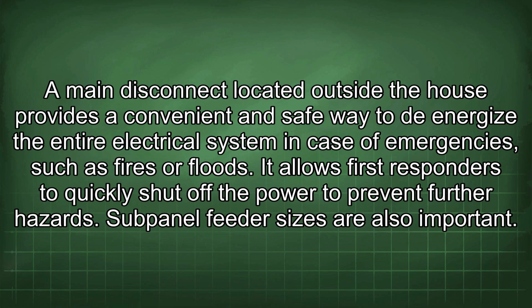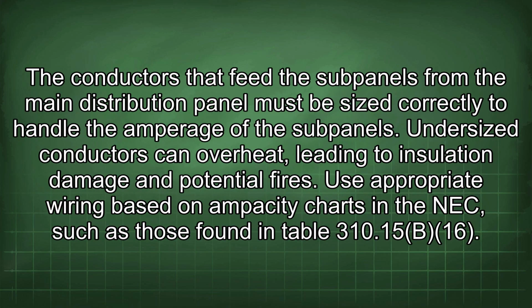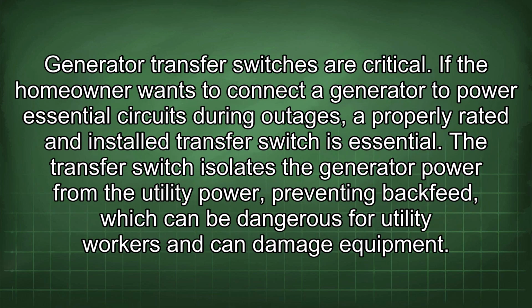Subpanel feeder sizes are also important. The conductors that feed the subpanels from the main distribution panel must be sized correctly to handle the amperage of the subpanels. Undersized conductors can overheat, leading to insulation damage and potential fires. Use appropriate wiring based on ampacity charts in the NEC, such as those found in Table 310.15(B)(16). Generator transfer switches are critical.